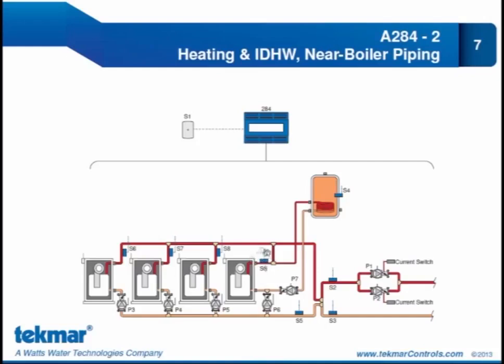Notice here that we have an outlet sensor for the 4th boiler, and we also have a domestic hot water sensor. Now this is different than what you might have noticed with the 275, 274, when this type of domestic hot water generation was referred to as mode 5. And in mode 5, in the previous generation of controls, we did not have a domestic hot water sensor. We measured the domestic hot water temperature from the boiler outlet sensor. So now we have changed this operation so that we can accommodate a domestic hot water sensor if we are doing this type of piping, which we refer to from now on as near boiler piping.